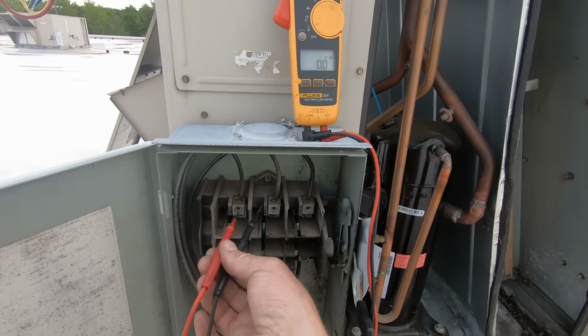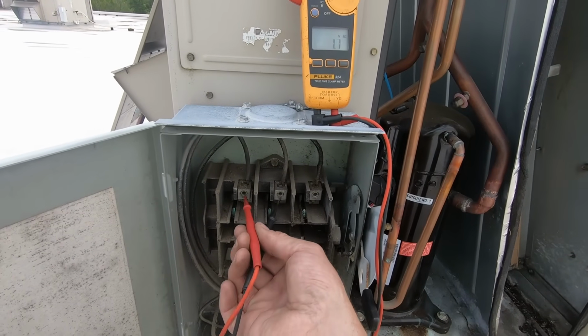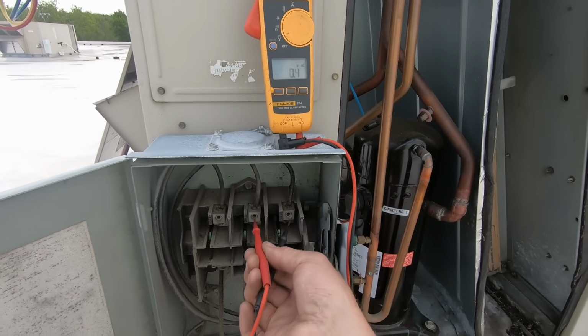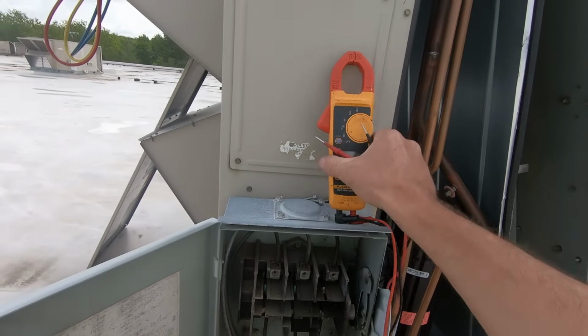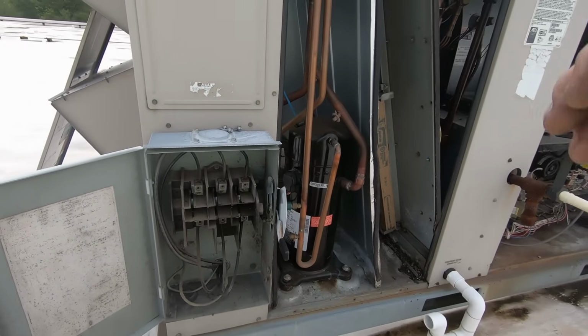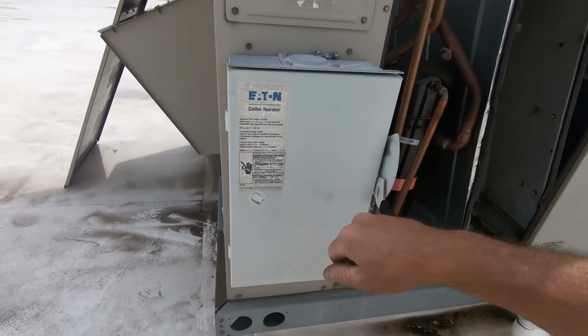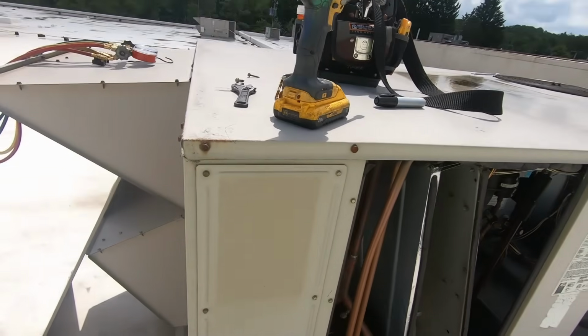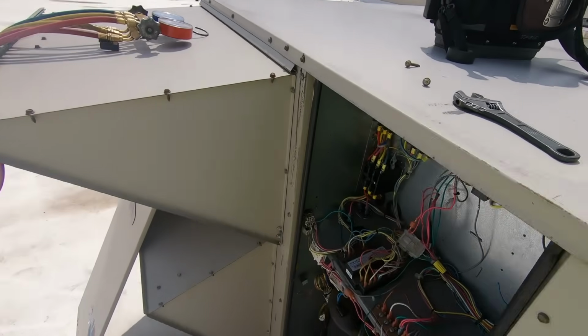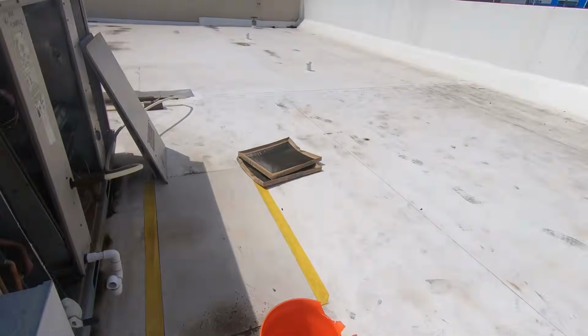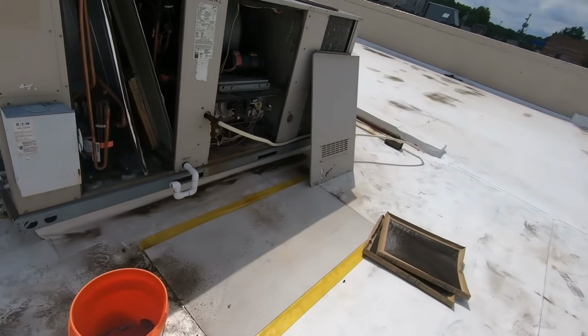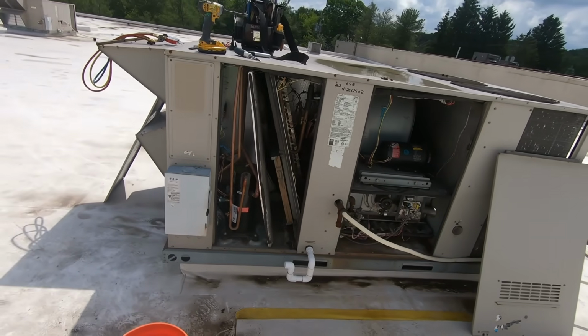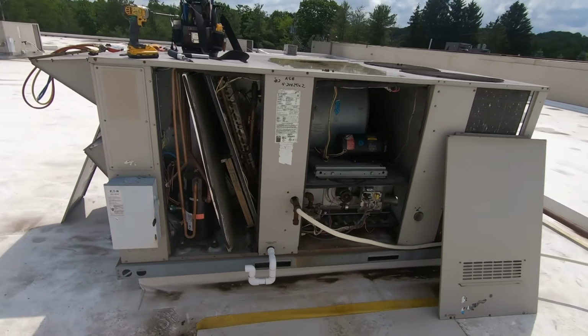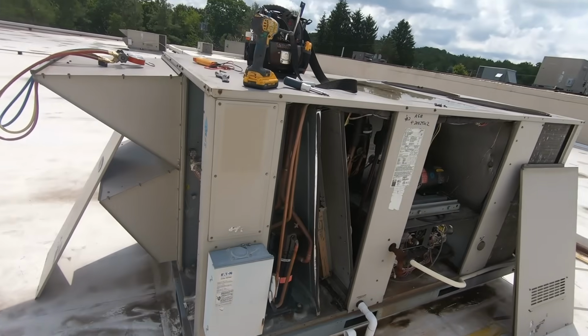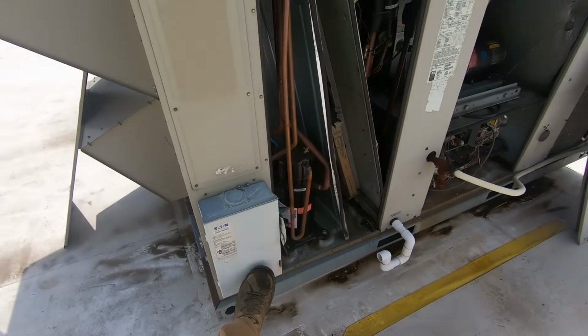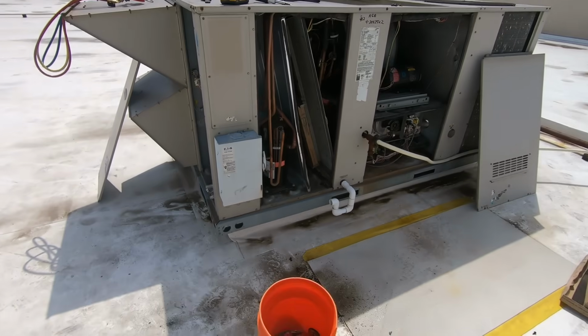Okay, so I found the disconnect inside and we have restored power. They're fused disconnects. It's like a disconnect wall, a whole panel, and there's no trip. You either blow a fuse and that's it. There's no tripping the switch, and the switch was in the off position. It took the manager about 20 minutes to clear out the bicycles and boxes. So I'm assuming they're using that room as storage and somebody knocked it and beat it with a box and switched that off, unless someone else switched it off. But why would they switch it off there when they've got a disconnect right here if there was an issue?